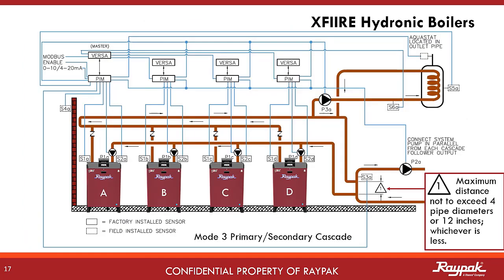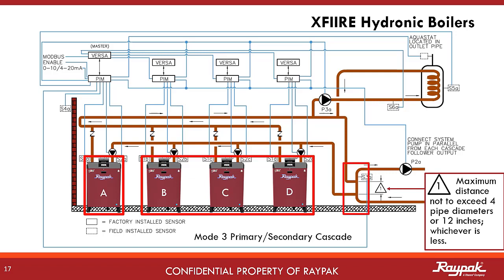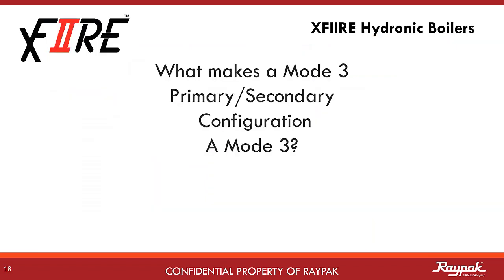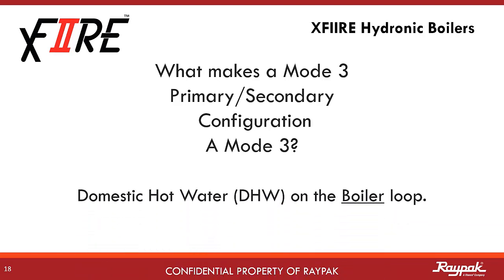Mode 3 can also be run in cascade. Here the A boiler is the master boiler and the others are followers. The decoupler supports the whole cascade. As with all boiler cascade systems, reverse-return plumbing logic applies. It's a Mode 3 because the indirect domestic hot water tank is out on the boiler loop. So what makes a Mode 3 a Mode 3? It must be plumbed primary-secondary and it must have an indirect domestic hot water system on the boiler loop.